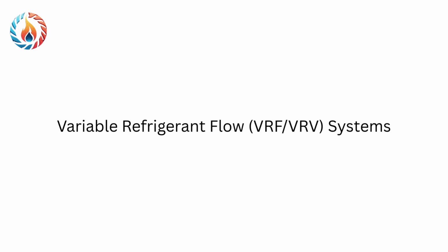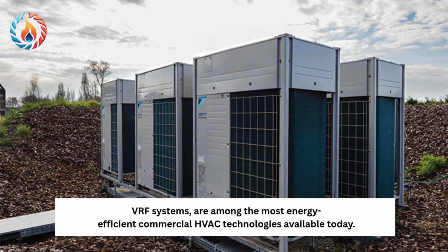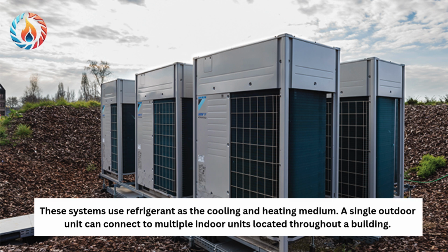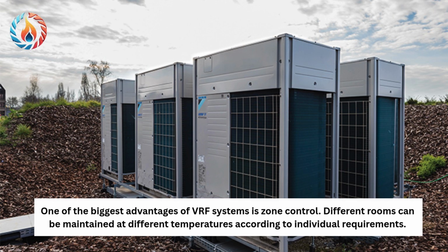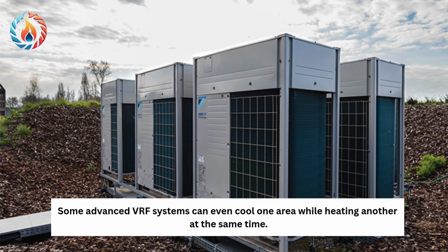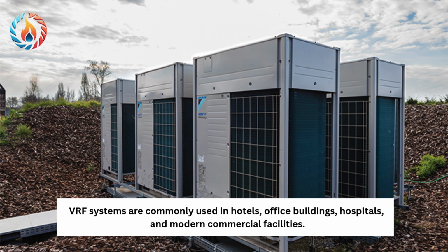Variable refrigerant flow, VRV systems. VRV systems are among the most energy-efficient commercial HVAC technologies available today. These systems use refrigerant as the cooling and heating medium. A single outdoor unit can connect to multiple indoor units located throughout a building. One of the biggest advantages of VRV systems is zone control. Different rooms can be maintained at different temperatures according to individual requirements. Some advanced VRV systems can even cool one area while heating another at the same time. VRV systems are commonly used in hotels, office buildings, hospitals, and modern commercial facilities.